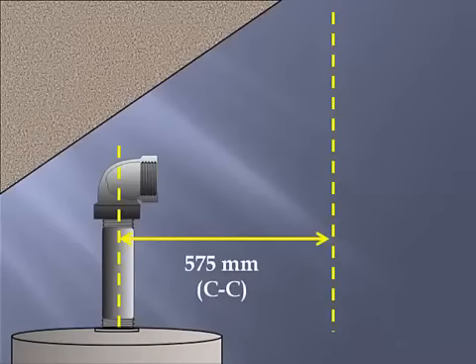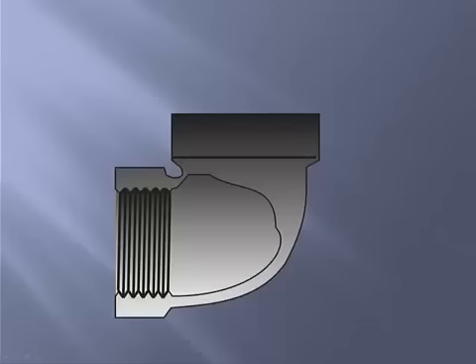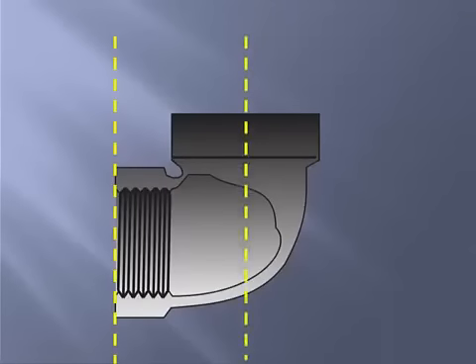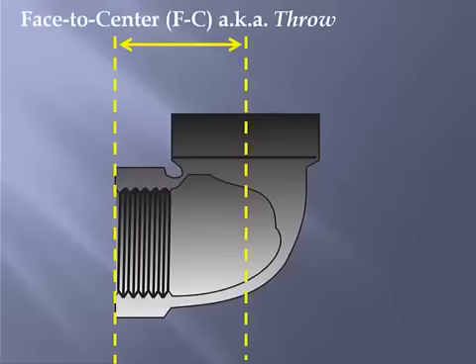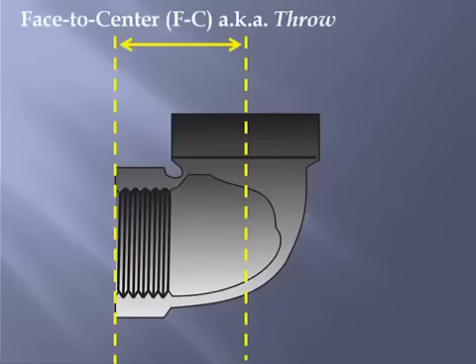Now let's take a look at the dimensions of a screwed fitting. The dimensions for screwed fittings are found in pipe trades training manuals or in manufacturer's literature. The typical dimensions given are face-to-center, also known as the throw, and the thread engagement. Now depending on the size of fitting, these dimensions will be different. Make sure you specify which fittings you are using and which dimensions should be used.